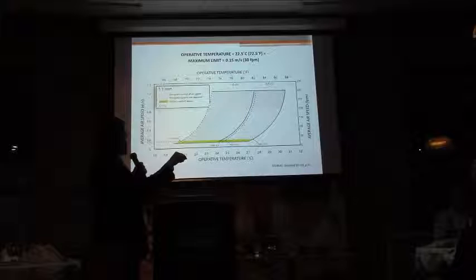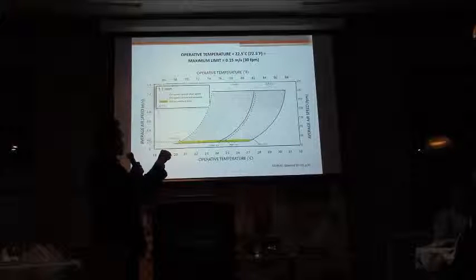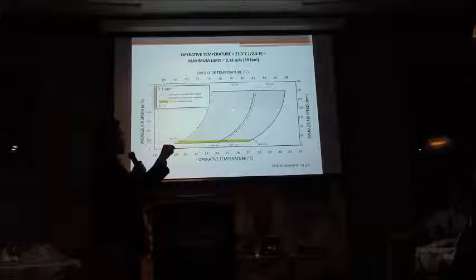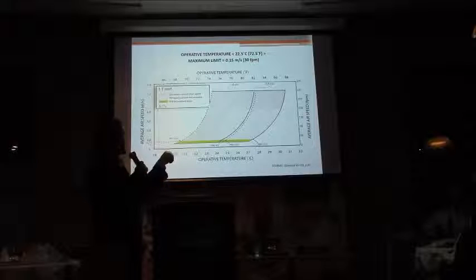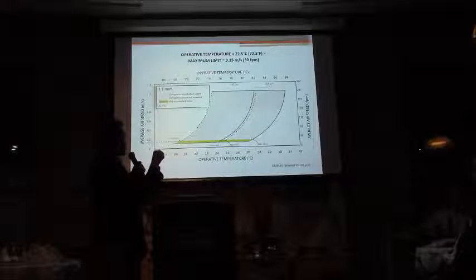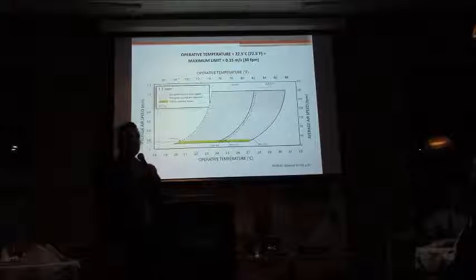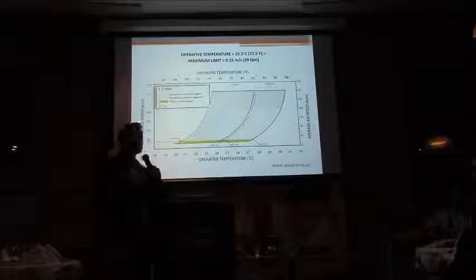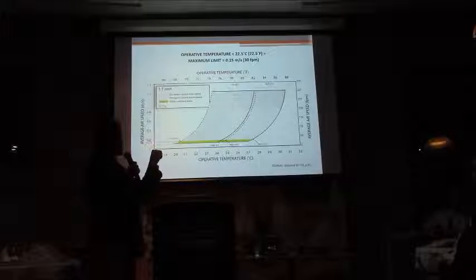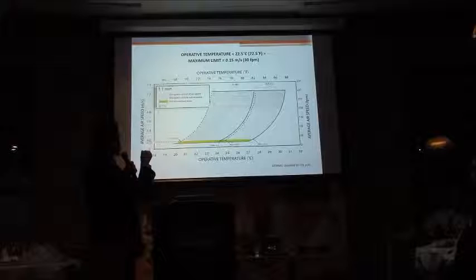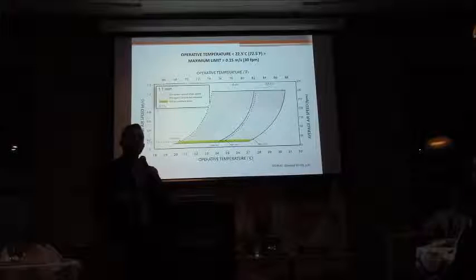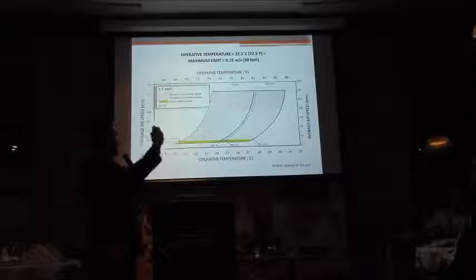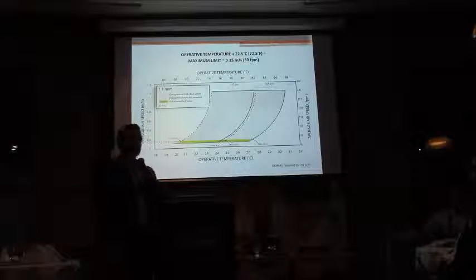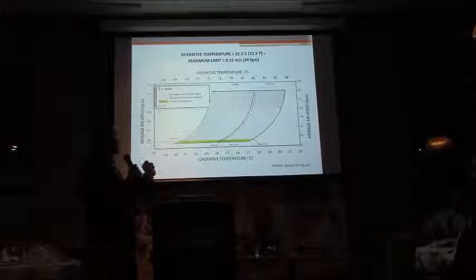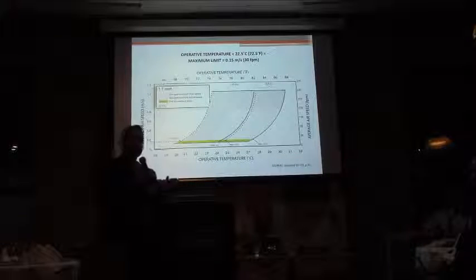And if you look here, if your temperature is higher than 22.5 degrees Celsius, 72.5 degrees Fahrenheit, you need to follow this line to know your maximum velocity, and it could be up to 160 feet per minute. But if you're under 22.5 degrees Celsius, which is most applications, and office applications are under 22.5, you need to be at a maximum of 30 feet per minute. That's 0.15 meters per second, which is the equivalent of 30 feet per minute. So ASHRAE goes as far as saying you need to have a maximum of 30 feet per minute if the temperature inside the room is 72.5 degrees Fahrenheit or less.